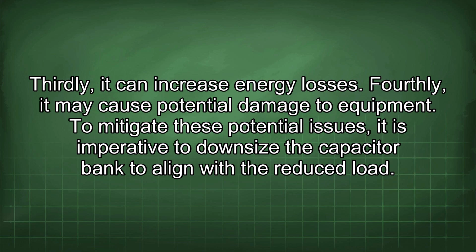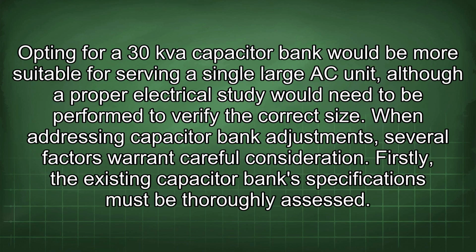To mitigate these potential issues, it is imperative to downsize the capacitor bank to align with the reduced load. Opting for a 30 kVA capacitor bank would be more suitable for serving a single large AC unit, although a proper electrical study would need to be performed to verify the correct size.